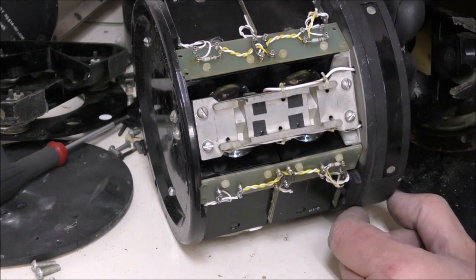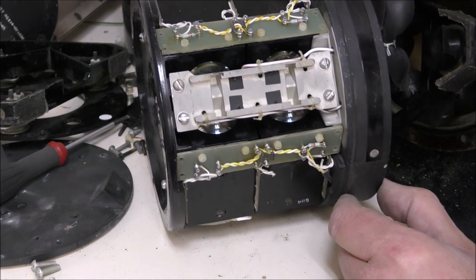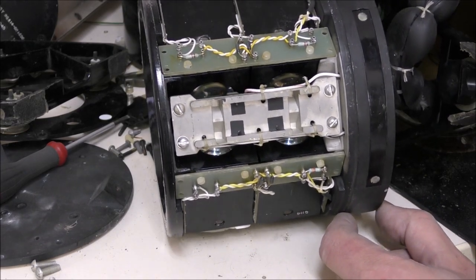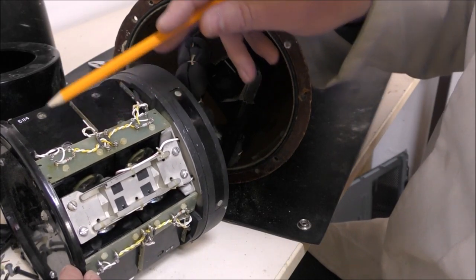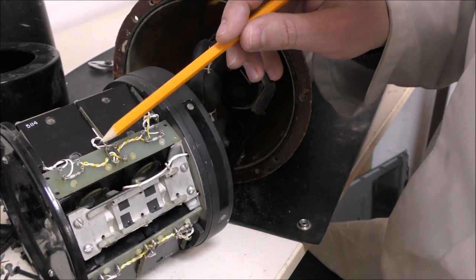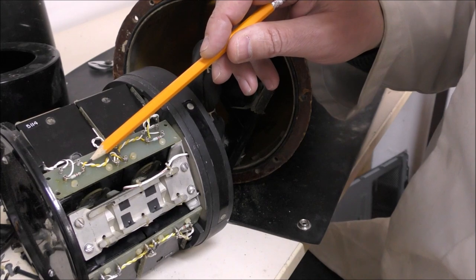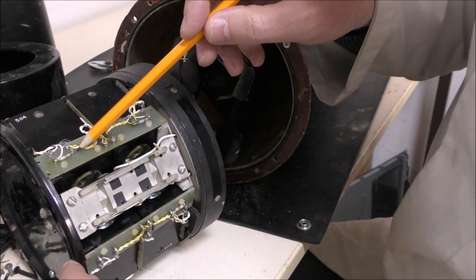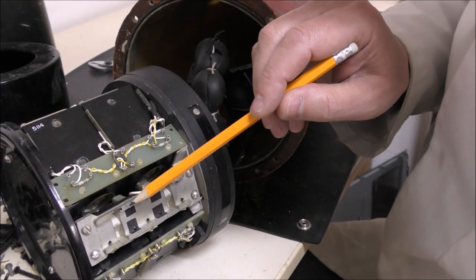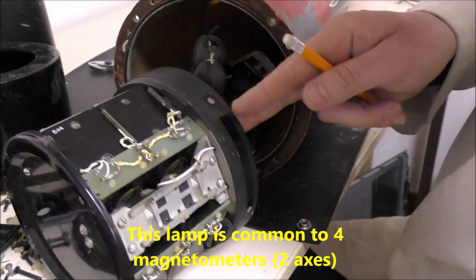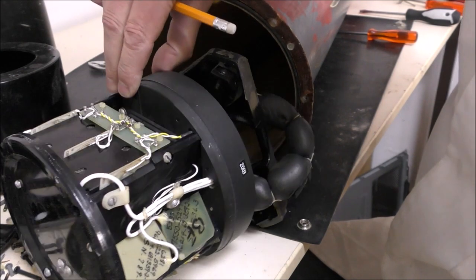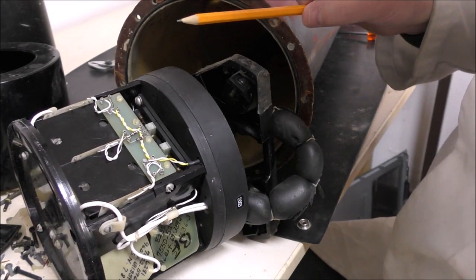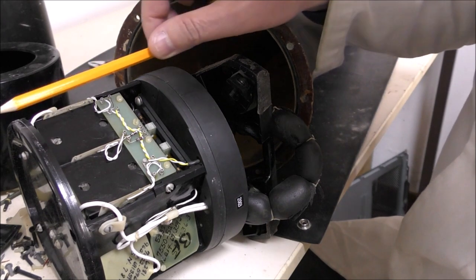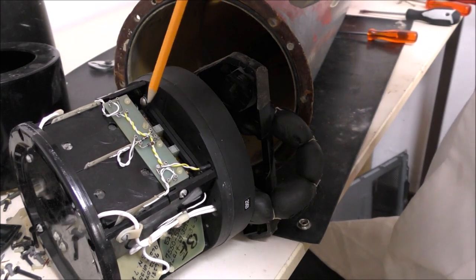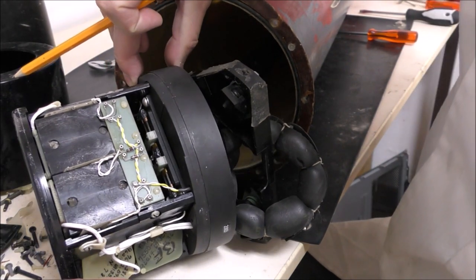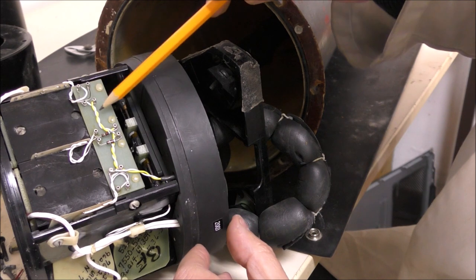Look at that — these are actually the magnetometers. You can see the lenses, so we have one sensor here on that axis, with twisted cables connected to a Helmholtz coil just behind it. You can see the lamp here — this is a helium lamp. It's difficult to see, but there's another lamp on the other axis, and this sensor measures the magnetic field in that direction. We try to zoom in — the helium cell is below this part.